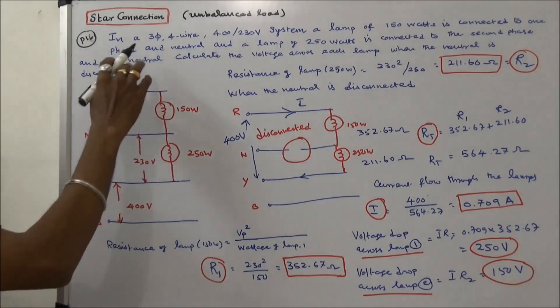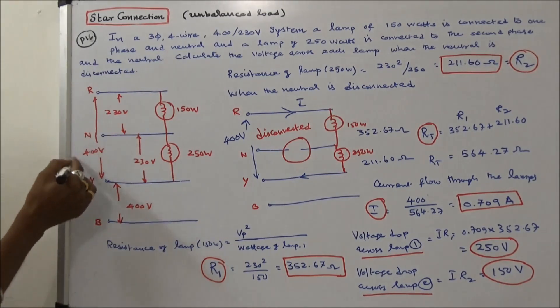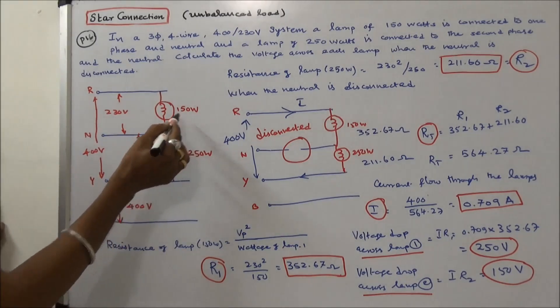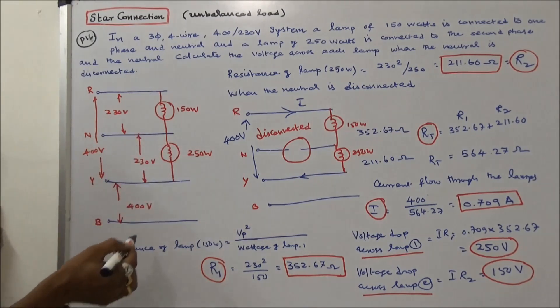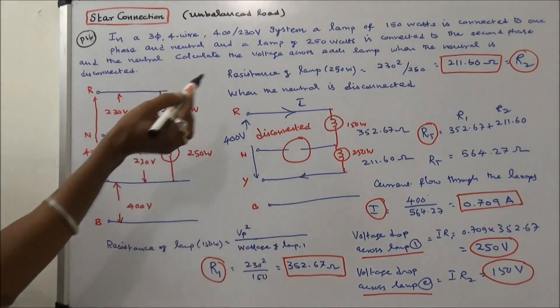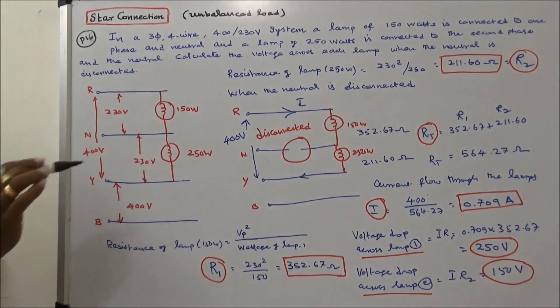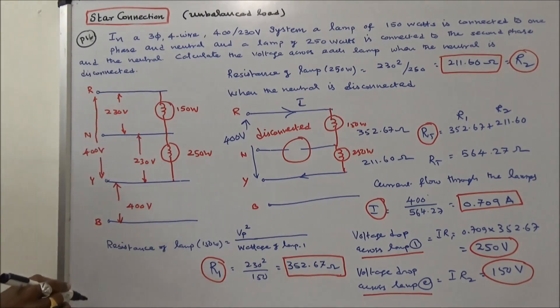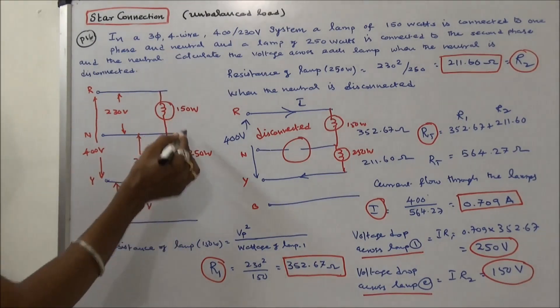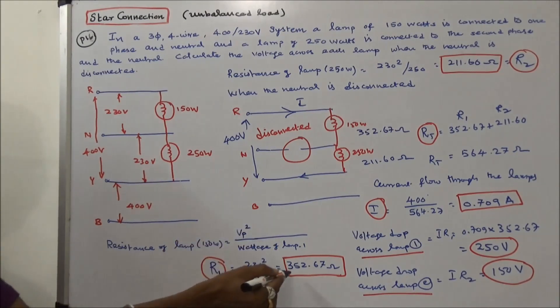Third problem. In a 3-phase 4-wire 400/230V system, a lamp of 150 watts is connected to one phase and the neutral. The question is: calculate the voltage across each lamp when the neutral is disconnected. First, calculate the resistance of lamp 1: R1 equals phase voltage squared divided by wattage, giving 230 squared divided by 150, equal to 352.67 ohms.